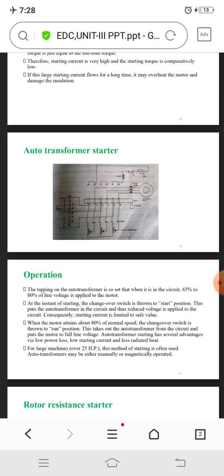Then starting of slip ring induction motor, rotor rheostat starter or rotor resistance starter. The slip ring motors are practically always started with full line voltage applied across the stator terminals. The value of starting current is adjusted by introducing a variable resistance in the rotor circuit. The controlling resistance is in the form of a rheostat connected in star, the resistance being gradually cut out of the rotor circuit as the motor gathers speed.